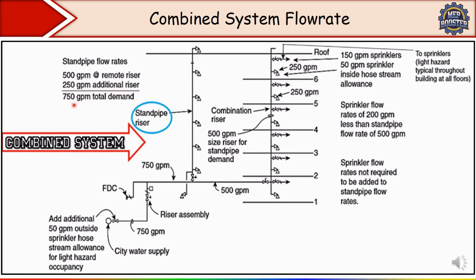So the total demand we have got for the standpipe flow rate is 750 GPM. 500 GPM is the required flow rate for the most hydraulically remote standpipe, and 250 GPM: if the system has more than one standpipe, each additional riser requires 250 GPM, as I told you, if your floor area is less than 80,000 square feet. So in total we have got 750 GPM, the sum of the standpipe demand, correct? So here we have calculated the standpipe flow rate, total 750. Now you need to calculate the sprinkler flow rate.